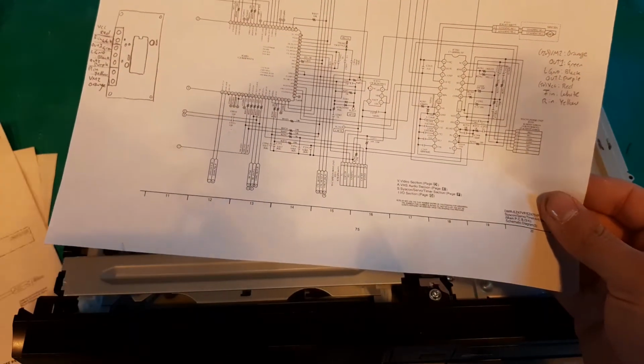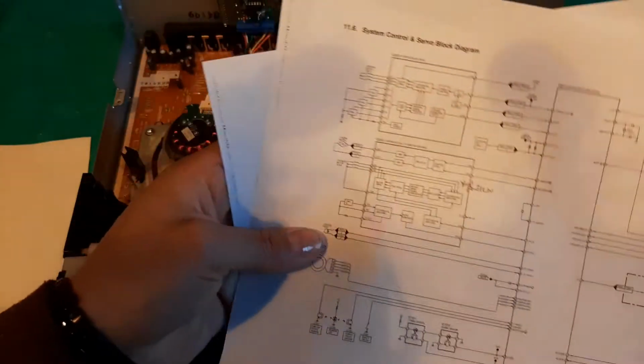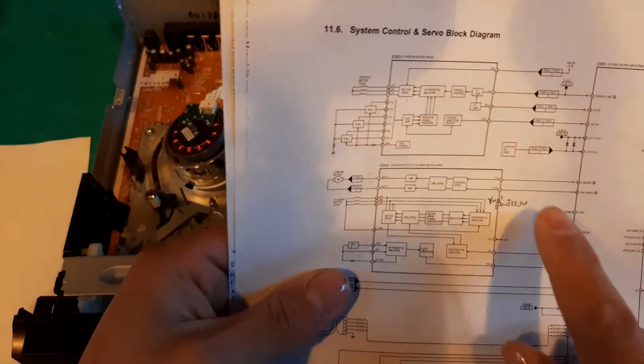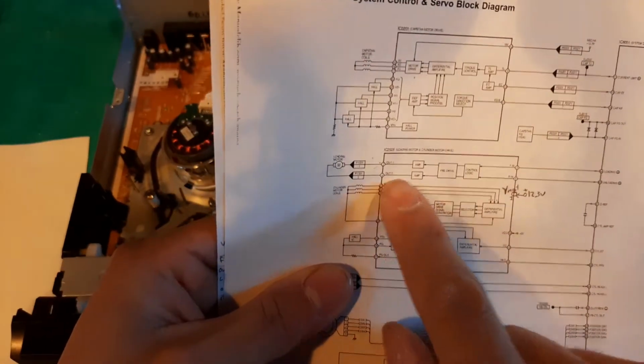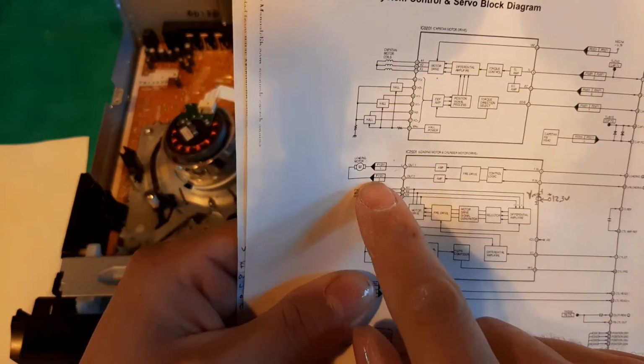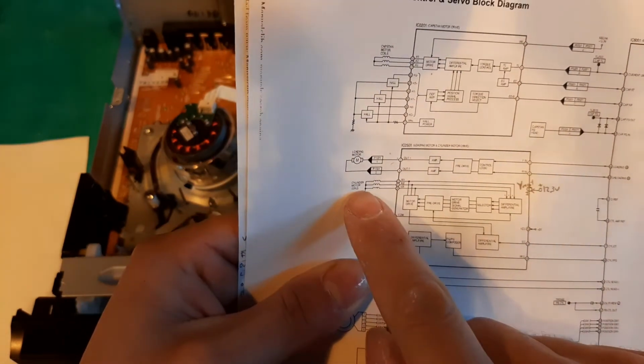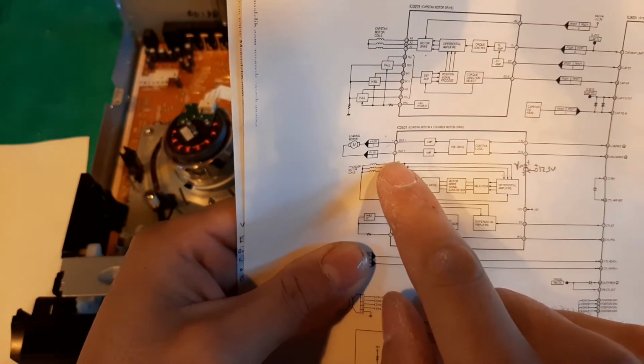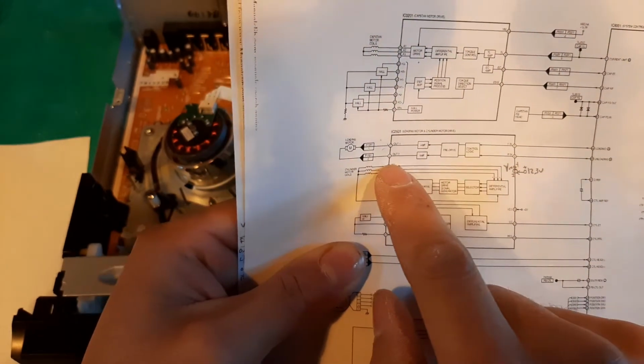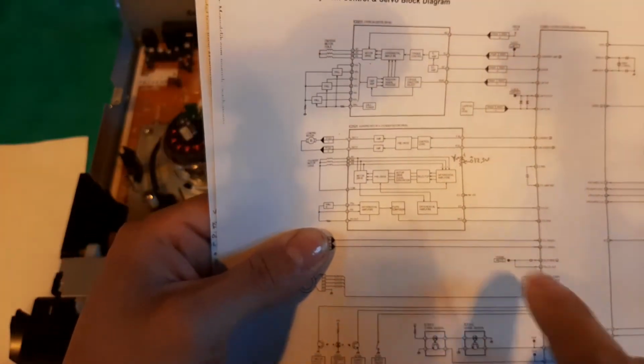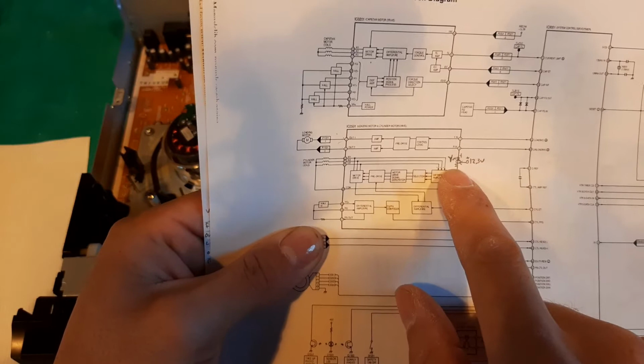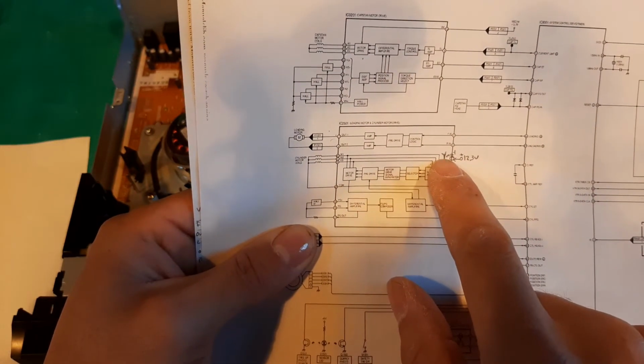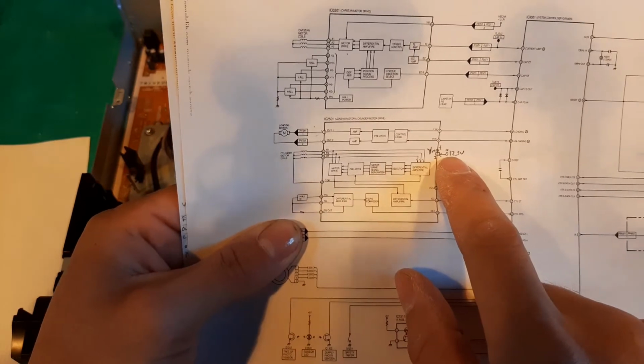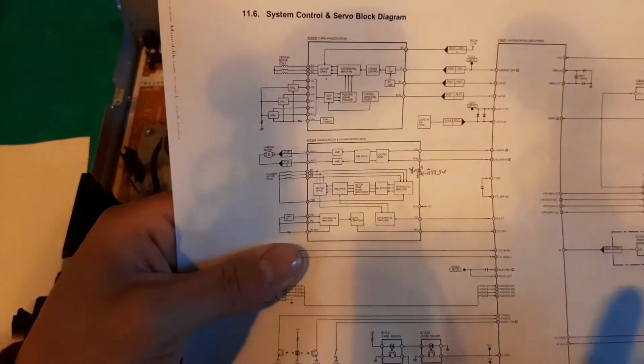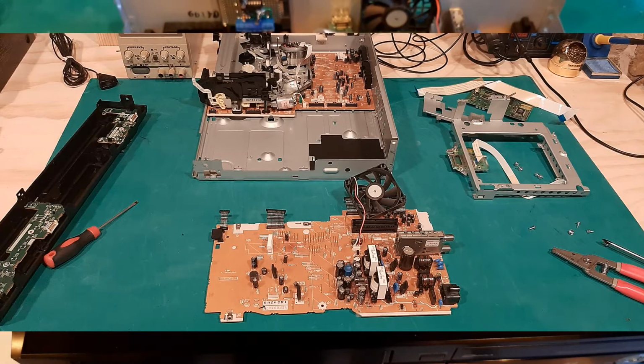On this diagram, in section 11.6, we can see the same chip, with the control circuitry for the loading and unloading motor on top, and the control circuitry for the cylinder motor on the bottom. The interesting thing is they have pretty much no interaction with each other, aside from some of the supply voltages. I noted that the drive motor voltage is supposed to be plus 12.3 volts.